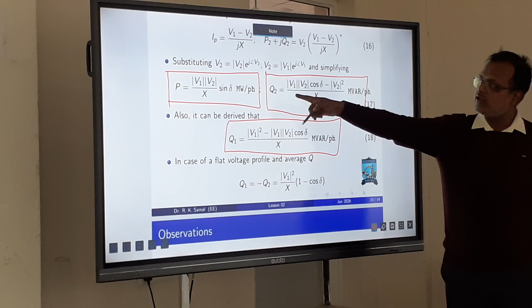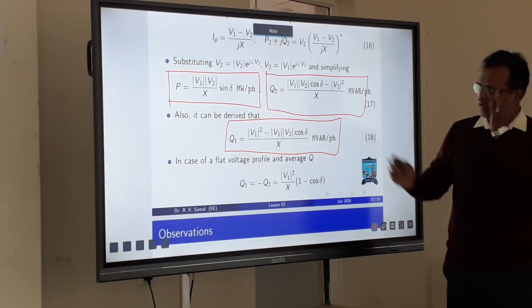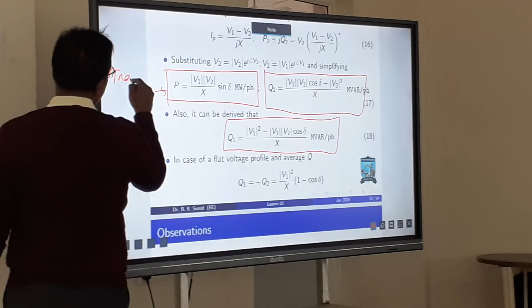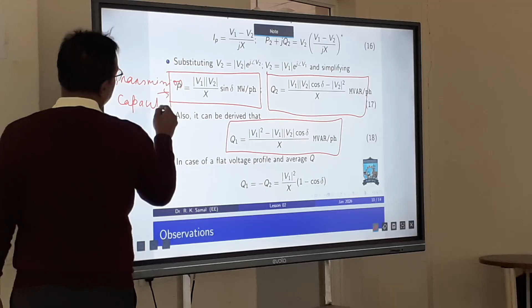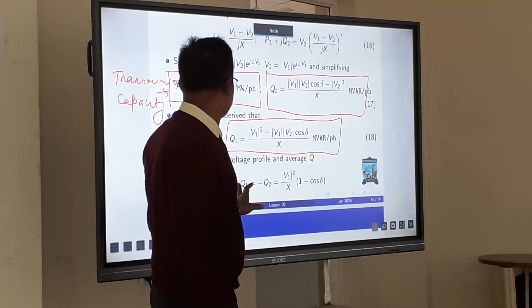Which also depends on the voltage. So Q2 means reactive power at the receiving end, Q1 means reactive power at the sending end. But this is not the transmission capacity. This is the transmission capacity. And to achieve this capacity, to keep the voltage fixed, we must have these two equivalent. So in case of a flat voltage profile, an average reactive power can be obtained, which is given by this. So these three formulas you write.